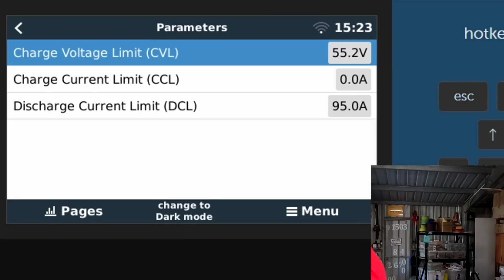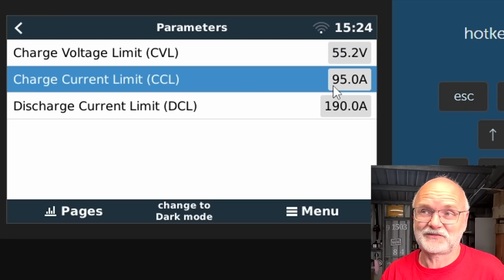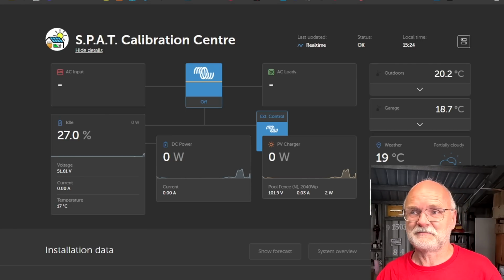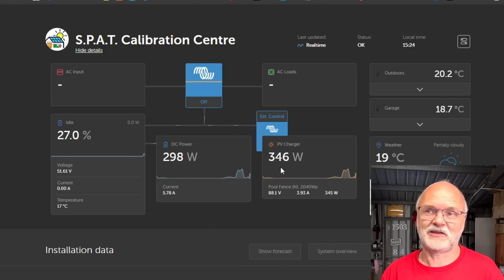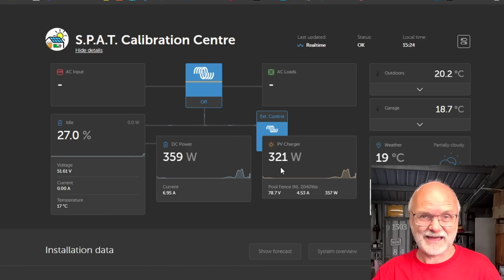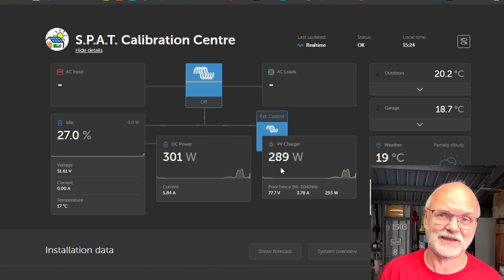Well, now you could argue, Andy, you have just shown us that it still reduces the charge current into this group of batteries if you have more than one in parallel. Yeah, I just connect the battery again. Okay, master and slave are connected again. And boom, immediately we still allow 95 amps into this group of batteries. The master is still on alarm, but here the alarm disappears. And you can also see the solar charge controller kicks back in, it starts charging, because the other battery, the slave, can still take the energy.